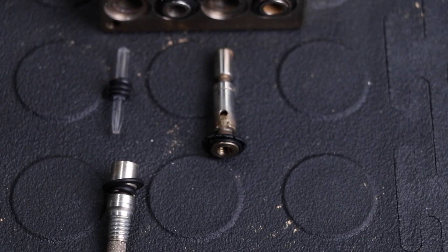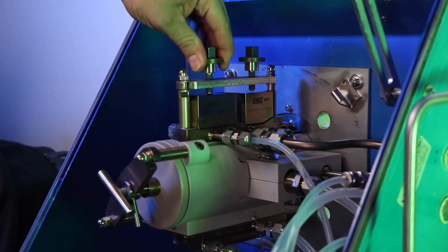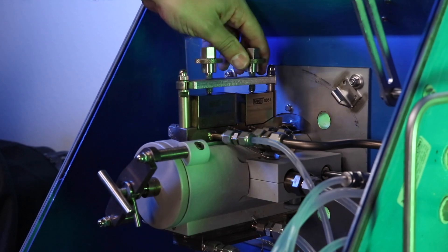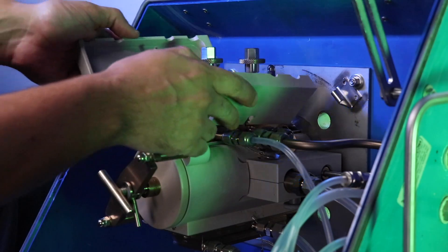One of the most important features of the SP2006 is the position of the dilution block. The dilution and eductor blocks, including the critical orifice, are mounted directly to the probe body and therefore heated up with the probe.